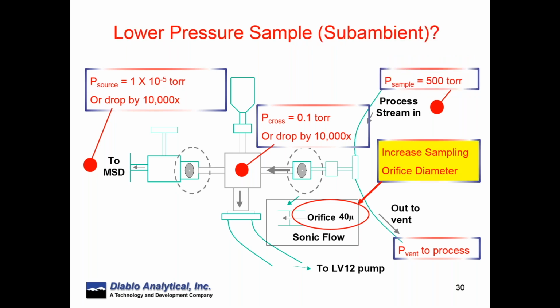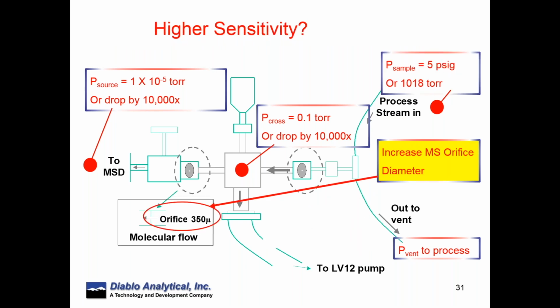And then, of course, this would be a vacuum, a subambient example, in which we're at 500 torr. So in this case, we could increase the diameter of the orifice from 30 microns to 40 microns. And again, the pressure would be about 1/10 of a torr in the cross, so the rest of the system then works in the same fashion. And of course, if we wanted to focus exclusively on some more sensitive or lower level components in our sample, we could increase the diameter of the second orifice, in this case, from 50 microns to 350 microns, and really allow more flow of sample into the mass spectrometer. So this is how you can easily manipulate and optimize the interface for your particular application.